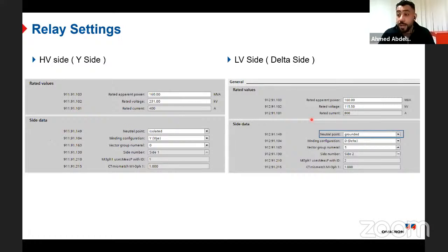The parameters of the transformer, as we said, we have the rated apparent power, we have the rated voltage. The rated voltage here is 231, the rated current is 400, 160, 115.5, and 800. And you can see here that I can even cover some cases which are not commonly available, you can say it's a niche application. Here I have a delta winding, but it is grounded with a zigzag transformer. With Test Universe, you can simulate this. It's very niche and also very unique, and special, by the way.